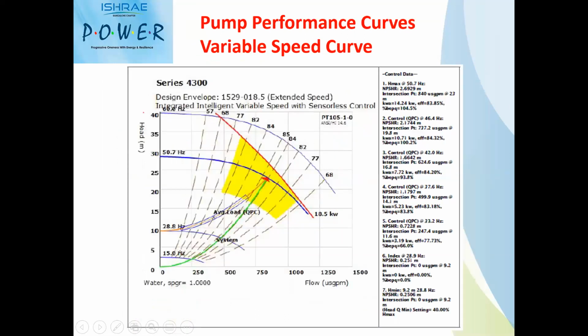When it comes to variable speed pumping, where the pump is being driven by a VFD, you need to have variable speed flow and head data, because 99% of the time we are operating a variable pumping system in our HVAC industry, where load keeps on varying and we keep on varying the speed of the pump, by which the flow and head data are controlled. So in this typical variable speed pumping, the pump always tends to operate along this green line, which is called a system resistance curve, along which the pump operates.